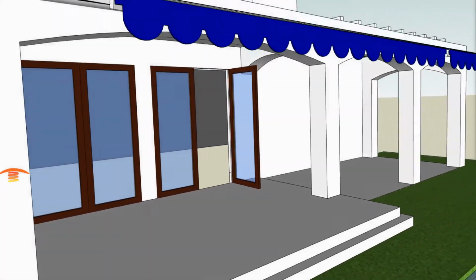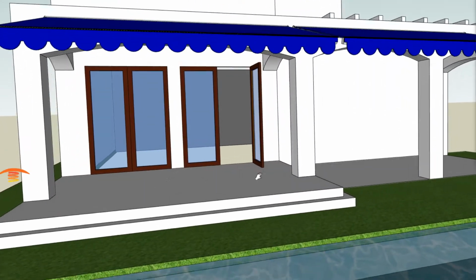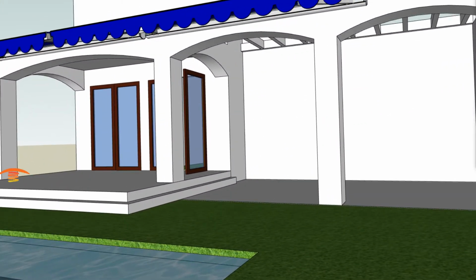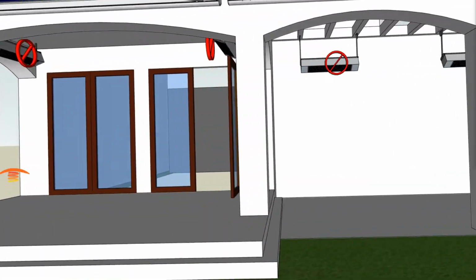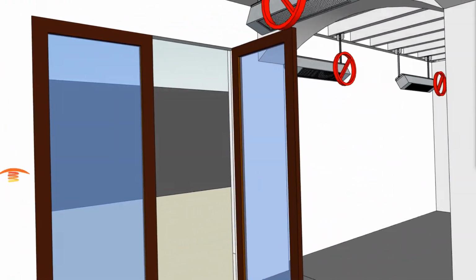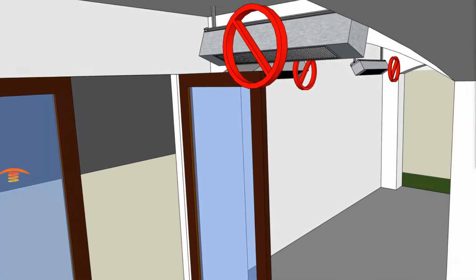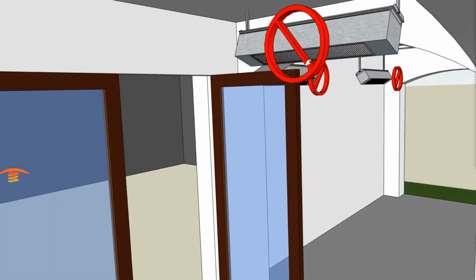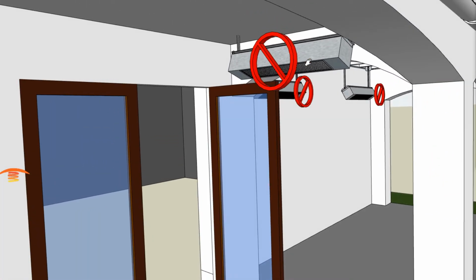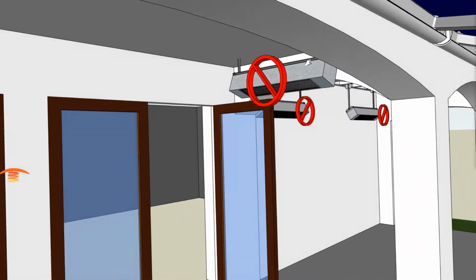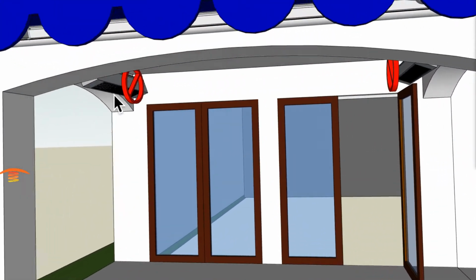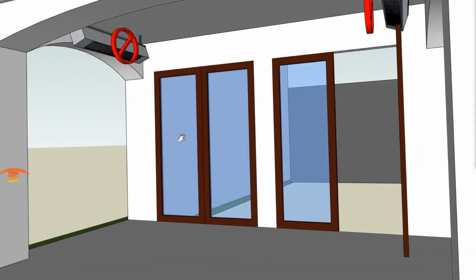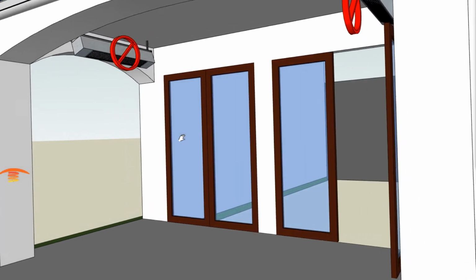As you can see here, we just have a straightforward two different level patio. So let's go ahead and just kind of talk about some of the stuff that they had that we didn't like. And I want to point out, number one, the first thing that really shocked me was this door opened, and if it was left open, it could be placed right underneath the heater, and that could be a tremendous fire hazard. And the same thing with the unit over here. If one of these doors was to be opened, then again, that's a big issue there.